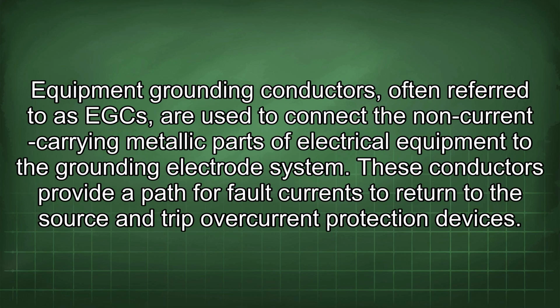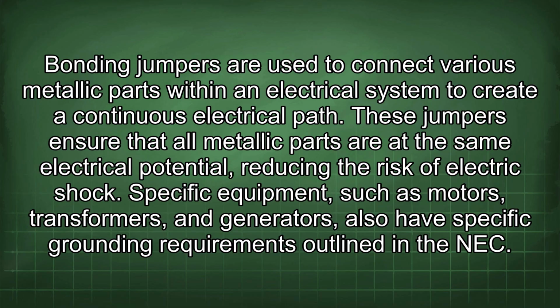Equipment grounding conductors, often referred to as EGC, are used to connect the non-current carrying metallic parts of electrical equipment to the grounding electrode system. These conductors provide a path for fault currents to return to the source and trip overcurrent protection devices. Bonding jumpers are used to connect various metallic parts within an electrical system to create a continuous electrical path. These jumpers ensure that all metallic parts are at the same electrical potential, reducing the risk of electric shock.